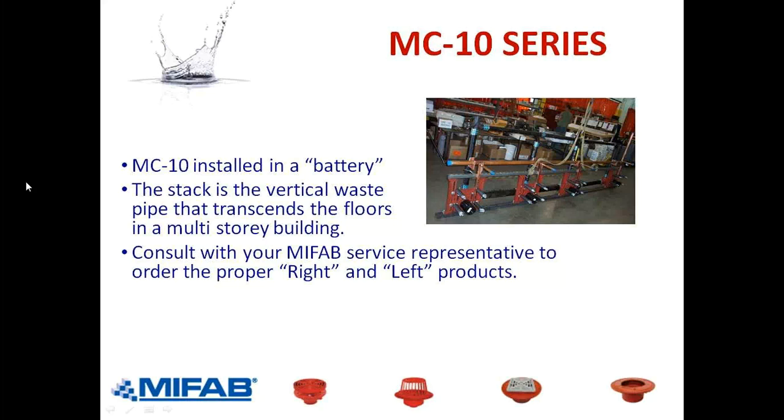When we talk about a row of carriers, we talk about a battery. This is a photo of MIFAB's MC-10 carriers installed at a contractor's prefab shop — you can see how they have cut pipe that goes between the carrier fittings, connected with no-hub couplings. A row of carriers is called a battery, and the stack is the vertical waste pipe that goes through the floors in a multi-story building. To know whether people need right or left-hand carriers, look at page 217 of your MPB book — you'll see MC-10Ls on the left and MC-10Rs on the right going to the stack in the middle, which contains the MC-13 vertical carrier.